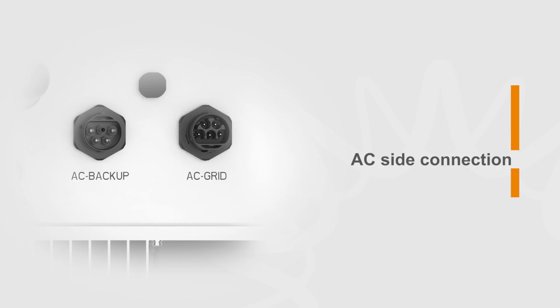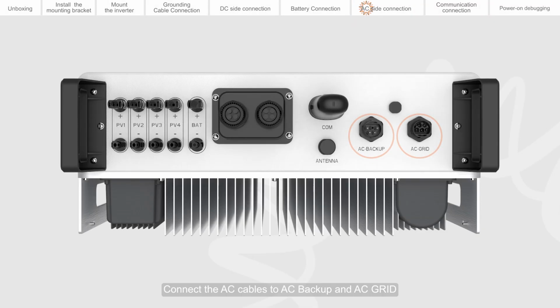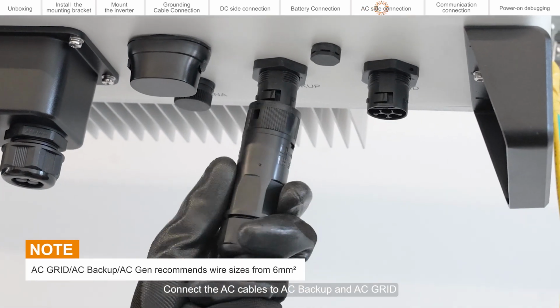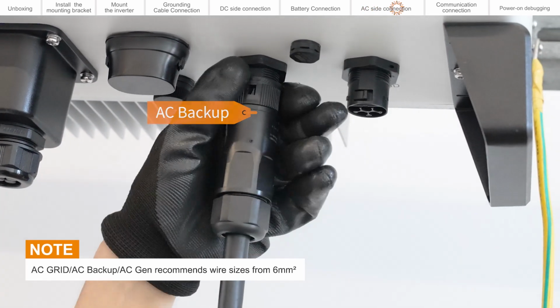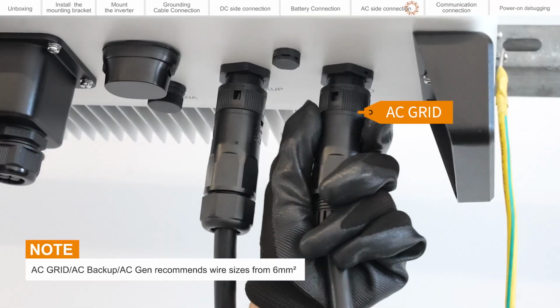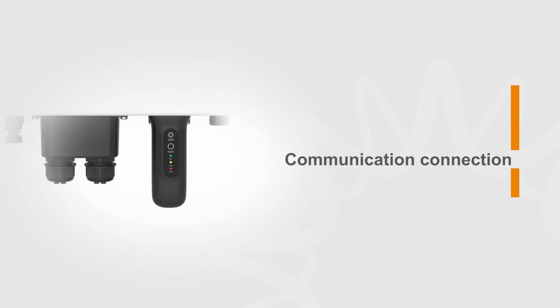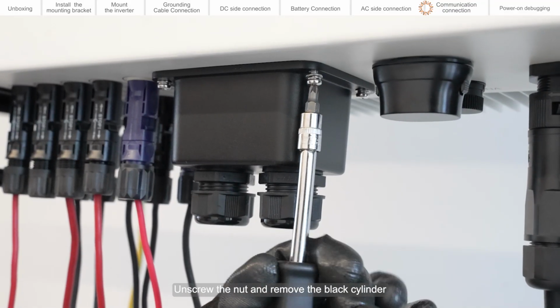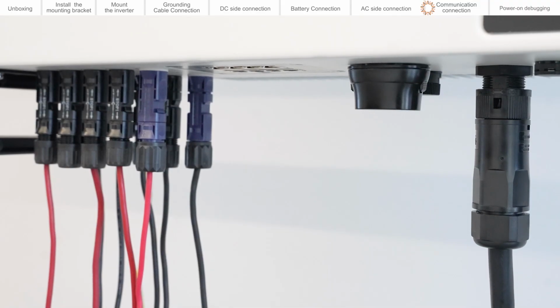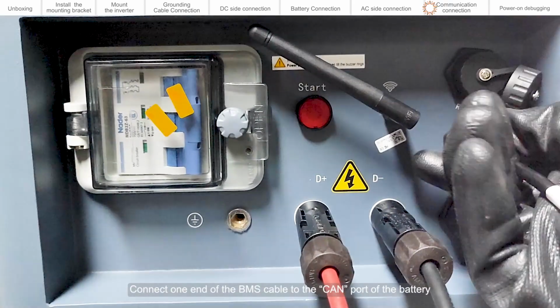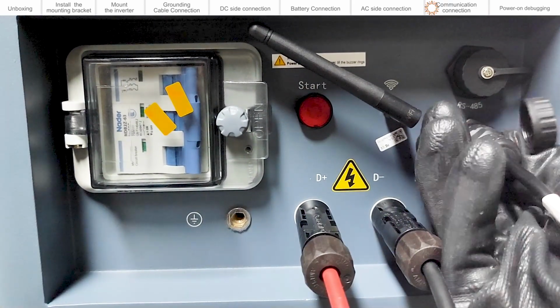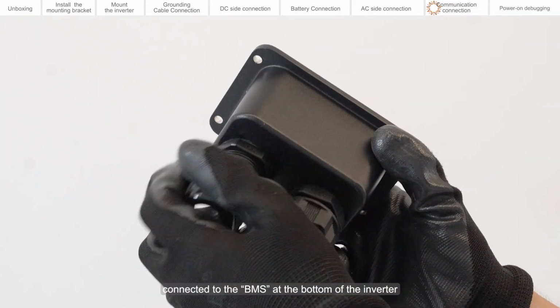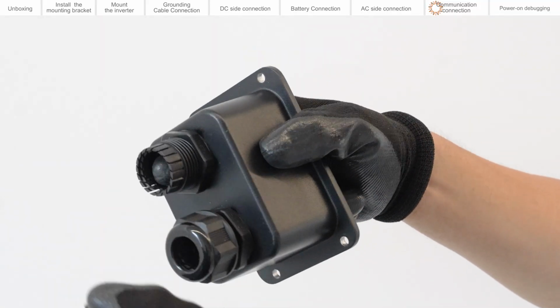AC side connection. Connect the AC cables to AC backup and AC grid. Communication connection. Unscrew the nut and remove the black cylinder. Connect one end of the BMS cable to the CAN port of the battery. Connect it to the BMS at the bottom of the inverter.